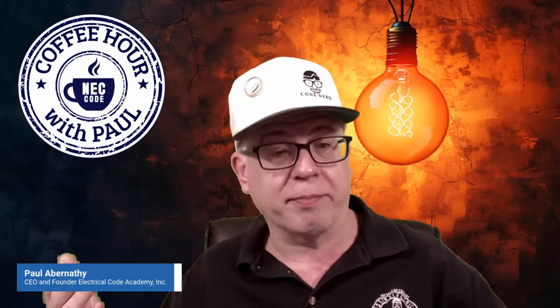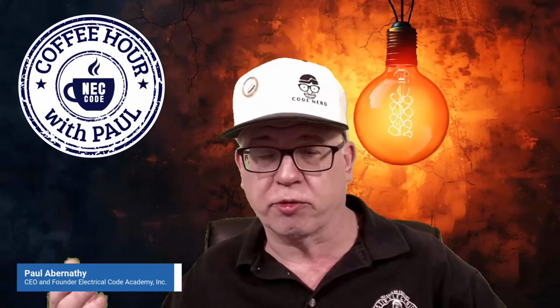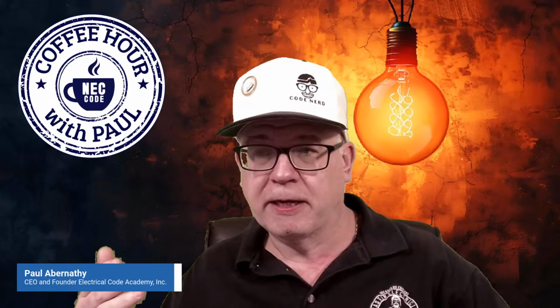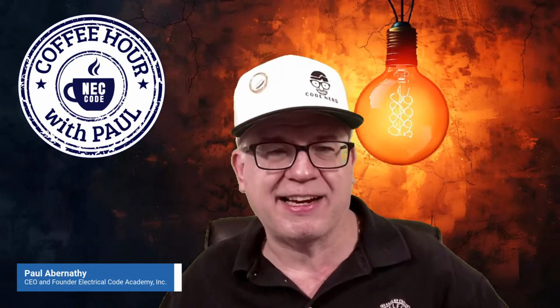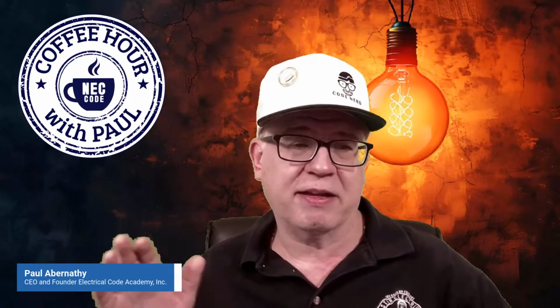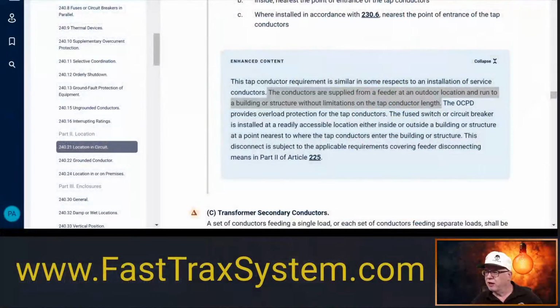The only voltage drop mandates, as you're aware, are for sensitive electronic equipment and fire pump applications, because we want that fire pump to run. We don't want it to burn up, so we're not trying to protect it in any way that type of thing. It still has short circuit and ground fault protection on it, but we want it to run until it burns up, that type of scenario. Okay. All right, let's go back here. So all right, that's all out of the way.